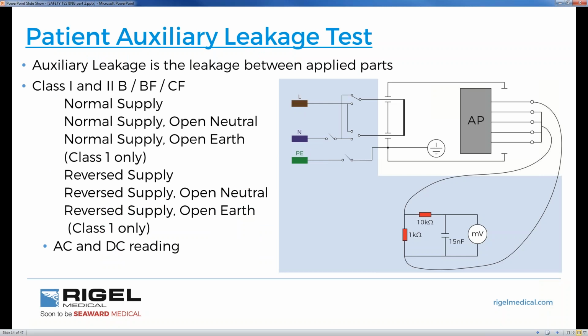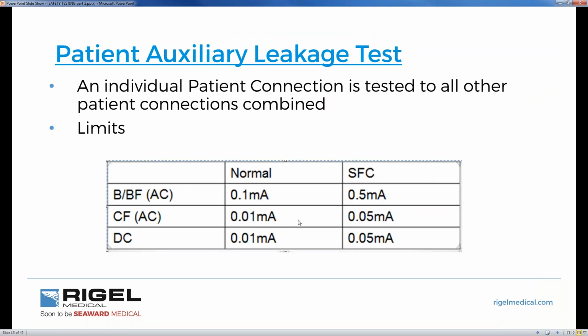Patient auxiliary leakage test is where we're measuring the leakage between applied parts. So we're not measuring to protective earth. If you have an ECG or another device that has multiple applied parts, patient connectors, what the Rigel device is doing is measuring any current that may flow between the applied parts via the 1K body model. It has the same pass-fail thresholds as patient leakage. An individual patient connection is tested to all the other patient connectors combined, something to bear in mind. This is done internally within the Rigel 288. All of the patient connections will be satisfied as per 60601.